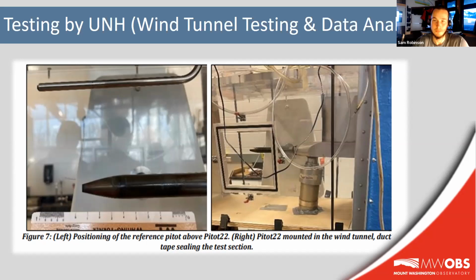And it should be known that while we were trying to simulate real wind experiences as closely as we possibly could, it is nearly impossible to do so in a lab setting. And at the end of the day, each anemometer is expected to read slightly different, as these are all different instruments and they're all unique in their own way. The wind tunnel was operated at a range of 0 to 130 miles per hour. And then we recorded that wind speed data through both pitot tubes.